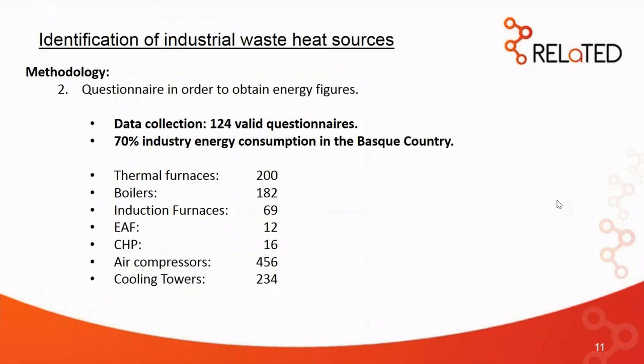Well, I guess reducing the temperature increases the cost effectiveness of using low grade heat sources. So by reducing the temperature lift that a heat pump would have to overcome, you can increase its efficiency, its COP. And having a lower temperature in the network means you have a more efficient network, because you've got lower heat losses.